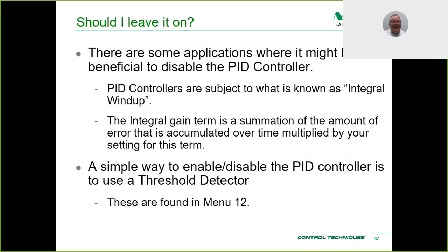Now the question is, should I leave the PID controller on at all times? Well, maybe, maybe not. There are some applications where it might be beneficial to disable the PID controller. As I referred to earlier today, PID controllers are subject to what's known as integral windup. The integral term is simply a sum of the amount of error accumulated over time multiplied by your gain term. So you can imagine if I left the PID on all the time, that integral term is going to cause a large value to accumulate, and I really don't need that. So I would advise selectively enabling and disabling the PID controller. And we can do that easily using what we call a threshold detector. Those threshold detectors are found in menu 12.